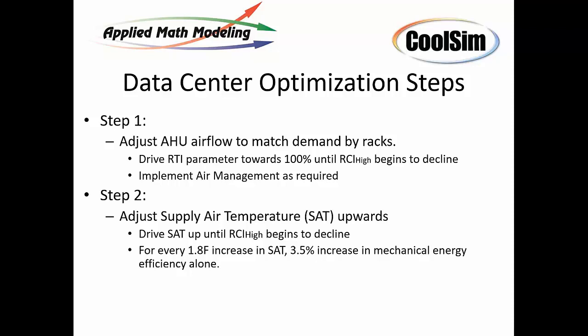So this is coarse, but it serves a purpose for first pass analysis, and the ability to model this behavior in mathematics is clear and evident in the work going on in this space. We're going to talk about that in a moment, and show you how we can do much better than just that. But remembering this ratio is important. You can think of it in C as well. It's a little easier in C because for every degree C, you get about 1% efficiency improvement. That's one that I use quite a bit, and it's useful. I'm going to use it here today.